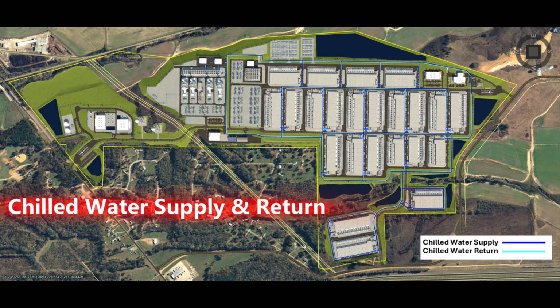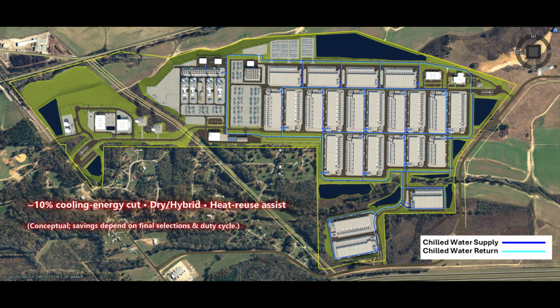Chilled water supply and return. Cooling is centralized and low water by design. We loop chilled water supply/return to the data halls and reuse secondary chiller heat where it helps. Using dry hybrid equipment trims water draw and delivers about a 10% reduction in cooling energy versus conventional evaporative plants, fewer chemicals, fewer visible plumes.